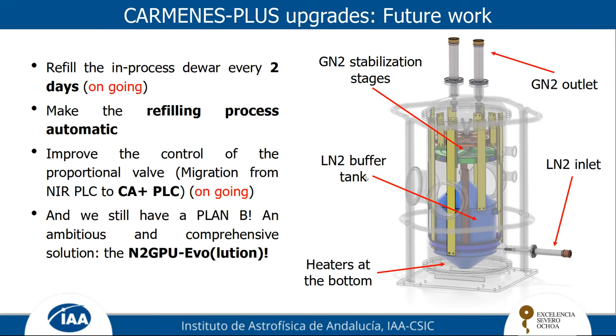What we want to achieve with this is that in case we don't evaporate all the liquid nitrogen, all the liquid goes to the bottom, so the gas can flow. Sometimes we had problems with the actual preparation unit because a lot of liquid stuck on the stage and the gas didn't flow very well. So this is the biggest upgrade, but there's a lot of differences because of all the things we have learned since the beginning of the instrument.